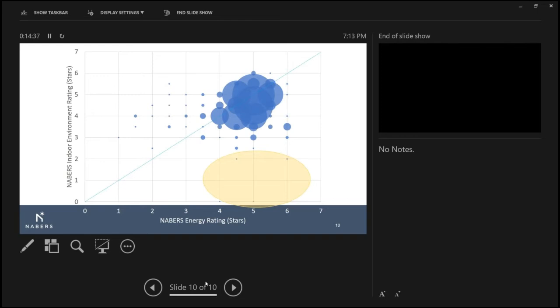So it's a question of whether that comes up in any of such analysis, or is that because the indoor quality is at a given point in time rather than dynamic, whereas energy efficiency is throughout the year. One of the things that we do is look at the annual temperature across the entire year. So we take 12 months of temperature data, eliminating weekends, public holidays, and times where people aren't in the office, with temperature readings at least every hour. Very often for the BMSs, we find that the data is every 15 minutes, so we get very granular data, and for BMS points across each of the sample floors to match what we are sampling in the spot measurements. So we're getting a really good temperature profile across the year, both for summer and winter, for compliant and non-compliant.